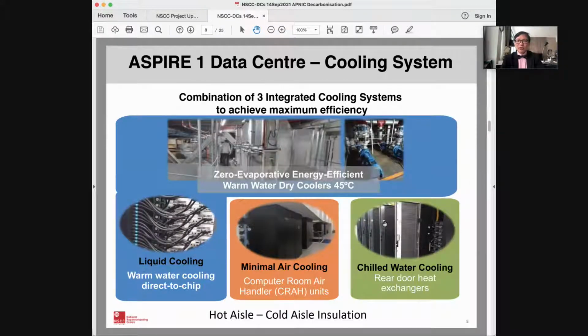We've also installed a combination of 3 integrated cooling systems: liquid cooling direct to chip to take heat out from the chips, minimizing air conditioning units, and rear door heat exchangers using chilled water to cool the data center racks. Most important, Singapore is an island with limited water resources—we cannot afford to evaporate water for cooling.